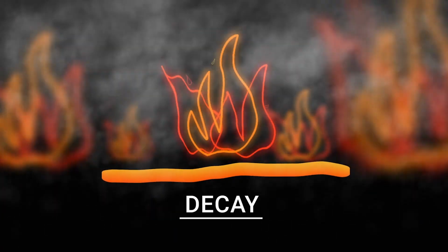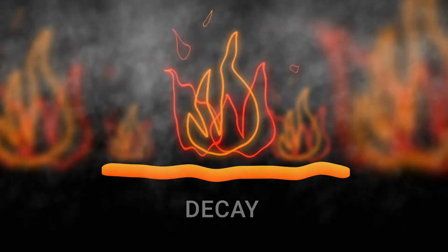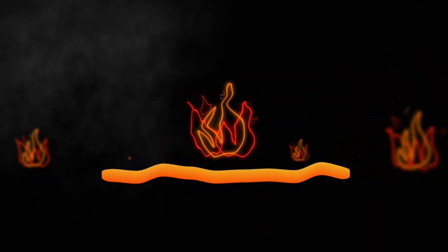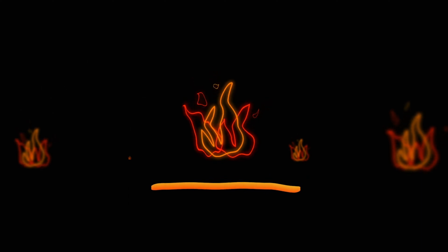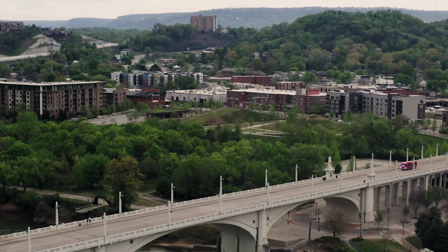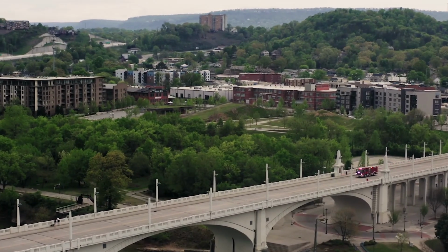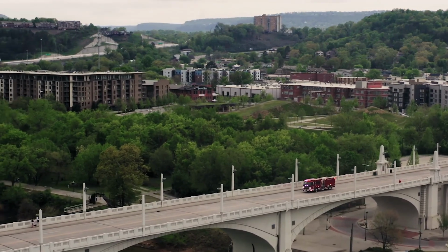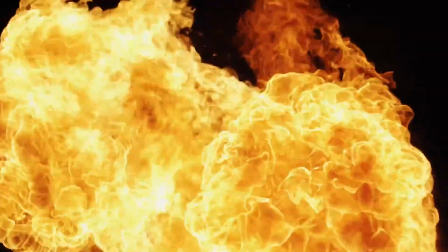Number 4. Fourth stage, decay, during which the fire tends to slow down due to the depletion of fuel sources, therefore causing the temperature to decrease. In order to minimize the potential of damage caused by a fire, any firefighting intervention needs to be carried out before the flashover. The flashover, as already mentioned, marks the transition to a fully developed fire, during which all fuel sources are engulfed by the fire.